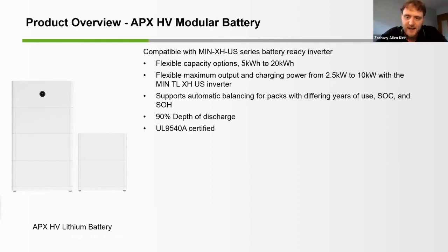It features a modular design to stack the battery capacity up to 20 kilowatt hours and the maximum discharge power up to 10 kilowatts. The modular design of this battery makes installation a true breeze and allows for greater flexibility for your customer system. The APX battery can be installed from floor to ceiling in one single battery cluster to save space on the wall, or it can be divided into multiple battery clusters. As we can see in this picture here, it's possible to have 2 battery clusters with the one, this is the main battery module optimizer. So this is what's handling all of the interfacing with the inverter. And then you can install that floor to ceiling, or you can split it into 2 separate clusters as shown.